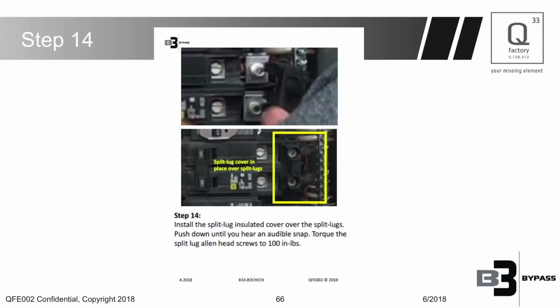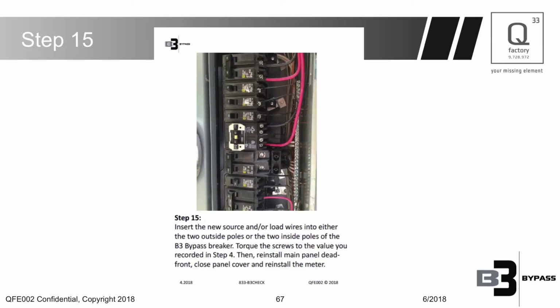After you do that, you put the insulation cover over the split lugs, that little plastic cover, and pop it into place. There are two sides to it. The long end goes on the outside. Just pop it into place, and then you're going to torque down those two hex screws to 100 inch-pounds, and you're done. Land whatever generation or loads you need to land to it, and it's fully installed.